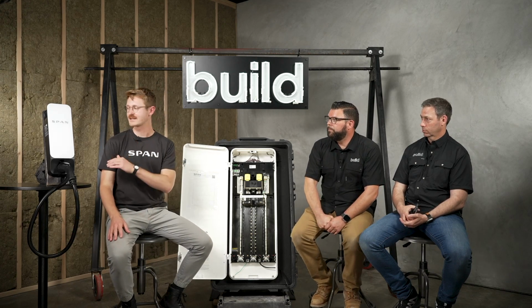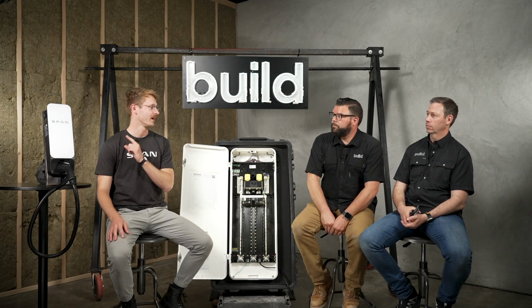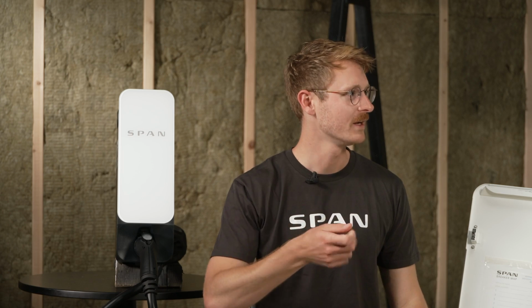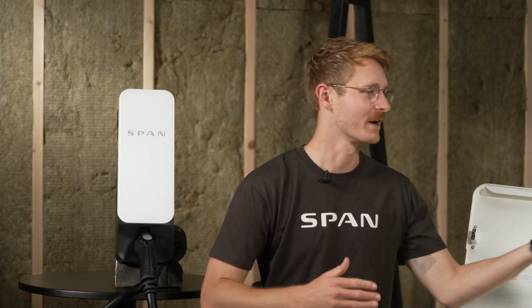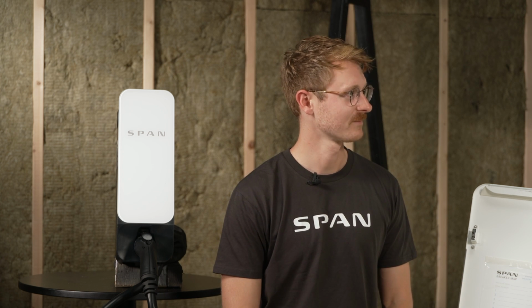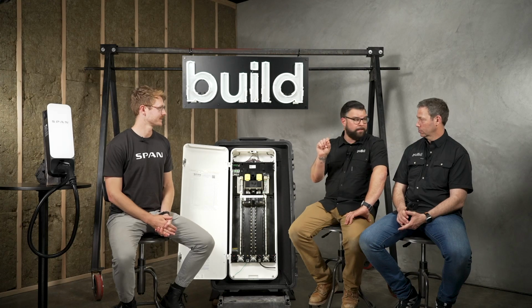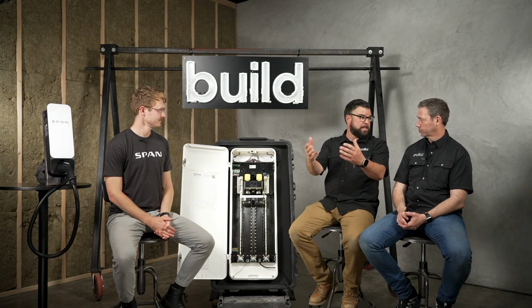Rather than setting a dip switch or dial at install to 20 amps because that's all the spreadsheet told you the EV could handle, other chargers require you to select what breaker you're feeding inside - you have to get inside, which most homeowners aren't going to do, and I wouldn't recommend. Plus the wiring from there to the EV charger is only rated for what they installed it for.